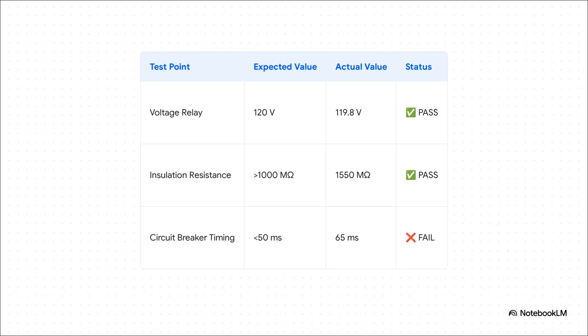This table shows you exactly what that logging looks like. You've got the expected value from the blueprints, and then the actual value, measured right there on site. The voltage relay passed, pretty much perfect. The insulation resistance, even better than expected. But then look at the circuit breaker timing—that's a fail. A circuit breaker is basically a gigantic, super-fast safety switch, and this one was too slow. On a power grid, a few milliseconds can be the difference between a tiny hiccup and a massive blackout.